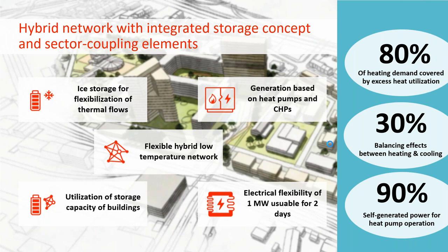The power generated in the 2 CHPs and some larger rooftop PV installations that we are planning have the potential to cover roughly around 90% of the power needed for the heat pump operation. The solution uses a highly innovative storage concept that is key for thermal optimization and smart sector integration. Three elements here are crucial. The large balancing unit set up likely as an ice storage for day-to-day flexibility. The thermal activation of the new buildings to utilize their thermal inertia on an intraday and day-night flexibility basis. And the utilization of buffer storage sites, very conventional at the generation units, for short-term flexibility.